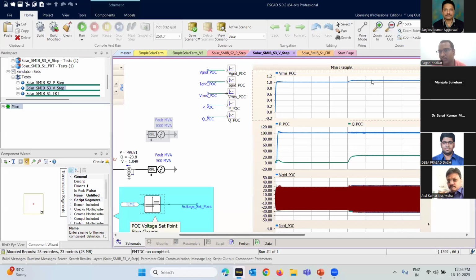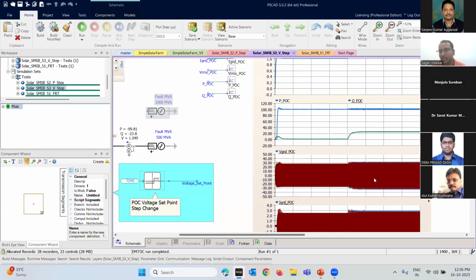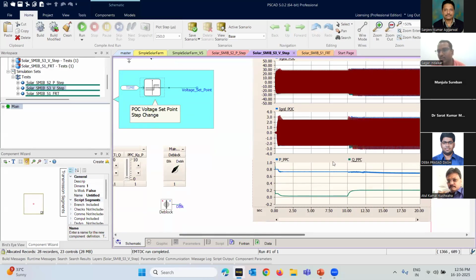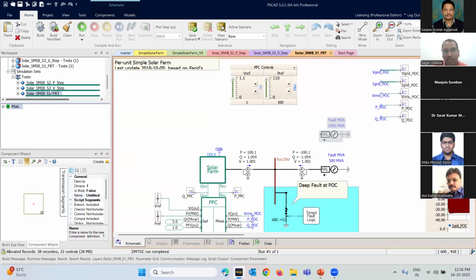And to increase this voltage, what does the inverter do? It will inject reactive power, right? So it will inject more reactive power so that this voltage is achieved. If we want to reduce the voltage, it will absorb reactive power. And these are your PPC commands. So blue is more or less constant, but Q has increased because the voltage set point was increased. Similarly, you have to perform reactive power set point changes and power factor set point changes and see whether the response has been correctly followed.